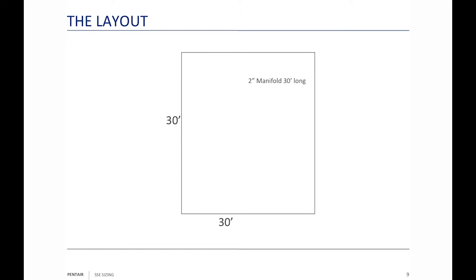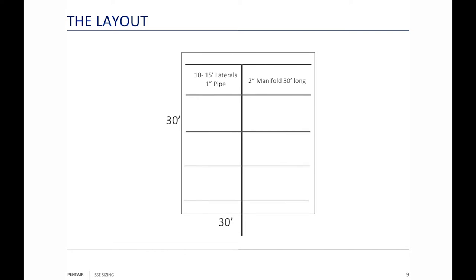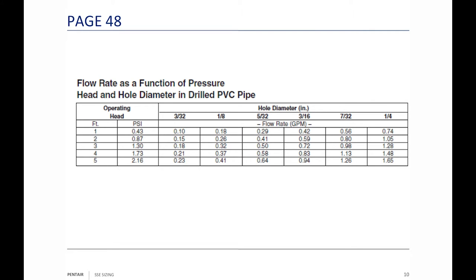For layout, we divide 900 square feet into a 30-by-30 bed. We're going to use a two-inch manifold 30 feet long in a middle manifold application, with two-inch pipe coming out to that manifold — so it's all two-inch pipe all the way. We'll put in 10 one-inch laterals that are 15 feet long, two on each side, five deep. We're choosing to put in seven 3/16-inch holes per lateral, spaced two feet apart.